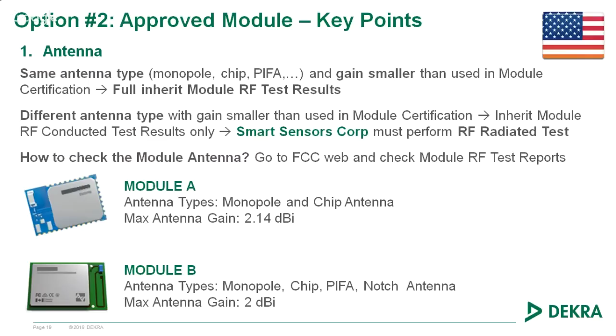And for the notified body, if I want to use one, I will only need to get the test reports from the module vendor, because the notified body needs to have all the information to make the assessment. For the USA, the requirements are similar, but typically FCC has a certification process with stricter rules. In Europe, at the end of the day, the responsibility of testing and making sure that the device complies with all the requirements remains with the vendor. In FCC, they have clear rules, and for instance, for Bluetooth devices, for non-licensed transmitters, they request that the antenna that you use in the integration has a lower gain, and it must be the same type of antenna, in order to be able to inherit all the RF testing from the module and save cost.